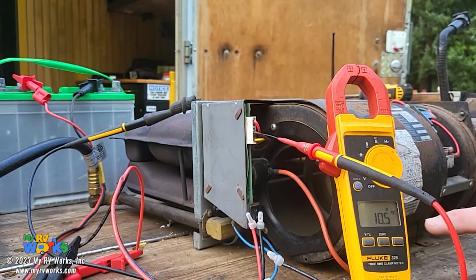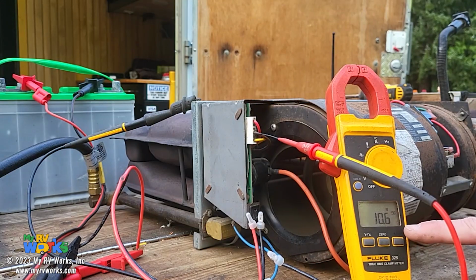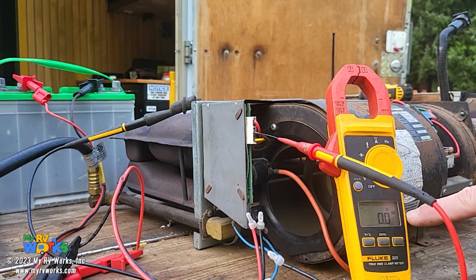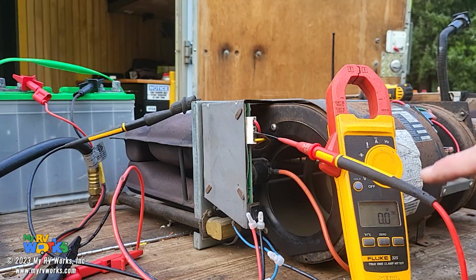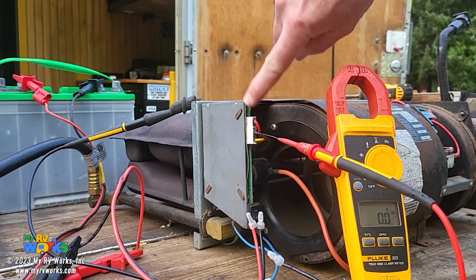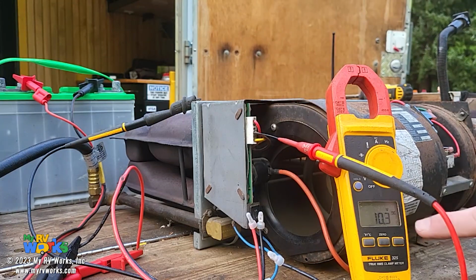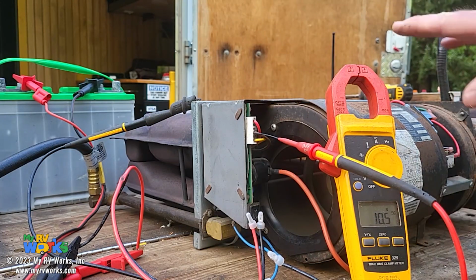Let me get it in there. Now I'm at 10.5 volts. The furnace is going through what's called a 3-second try. He's turned himself off, he's going to try 3 times, and he's going to go into soft lockout. We're referencing the brown wire here. He's going to try one more time. What's making this decision is this control board right here. The control board's going to energize him one more time, and after that he's going to say, all bets are off, I'm not going to try anymore.